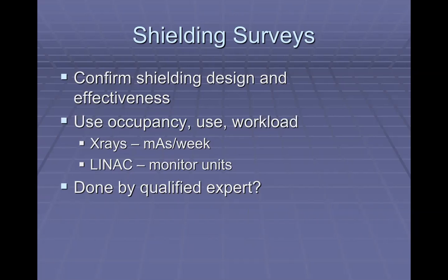So it's super important to actually take a meter and do these surveys. They have to be done by what's considered a qualified expert. Believe it or not, I'm not a qualified expert in the eyes of New York State. So I have to have all these surveys that I do personally signed off by a licensed medical physicist. It's a process to get your license, but honestly, how it pans out in real life is you do the survey, you get it reviewed by a higher up, and they sign off on it. But yeah, so it's taken very seriously, these surveys.